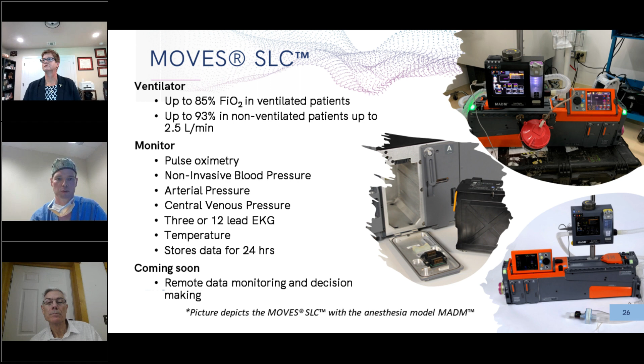And the ventilator, just so you can see there, it's able to give up to 85% pure oxygen in ventilated patients. If you're not ventilating, just using it kind of like a supplemental, like nasal cannula, it can be up to 93%. It can flow at about 2.5 liters a minute. So a smaller oxygen generator, but it is capable of doing it.